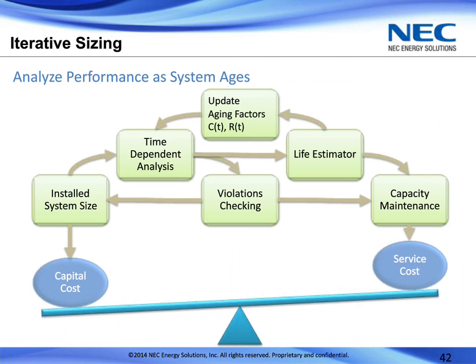The slightly more graphical representation of this, the top part of the slide, is talking about that whole modeling process, balancing the trade-offs between installed system size and how the system performs over time, how it ages, how many violations you're receiving, and potentially on the right side of this, how do you manage the capacity of the project over time? As the energy fades, do you need to supplement that over time? And then the underlying things that you're trading off from an owner perspective are the capital cost versus the service costs over the life of the project.